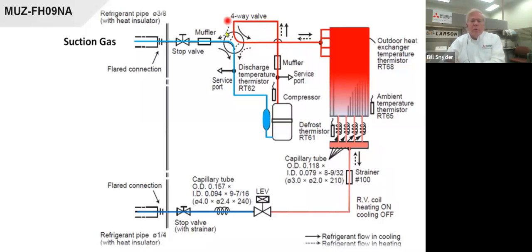So we have mufflers. That's what all of these capillary tubes are. They're getting rid of any pulsations and so forth in the system to try to make it as quiet as could be. There's another capillary tube here. We're actually doing most of the refrigerant control with a linear expansion valve. These are getting rid of some pulses and things that could cause some noise in the indoor unit. So this works very similar. We just don't have that heat exchanger circuit like we did on the hyperheat models.